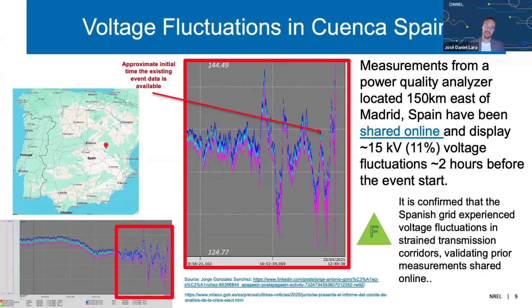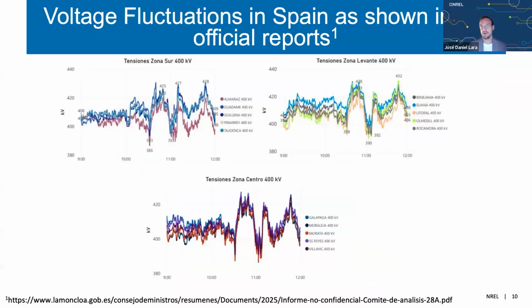Now we have confirmed it, given the data and measurements from the official reports, that these voltage oscillations and fluctuations actually happened. These were some of the original screenshots that were shared, and now we can see from the official report of the Spanish operator this same pattern of fluctuations across the system. If you look at the timestamps in the report, there were heavy variations in voltage starting as far back as 10:30 in the morning. So what we observe is that even though the focus of the study and conversation around this blackout was close to the time the oscillations happened, voltage problems were already going on in the system several hours before the actual event.